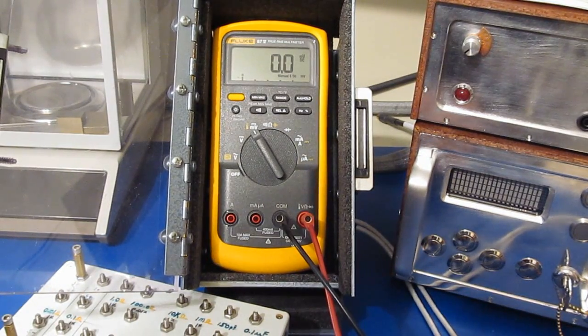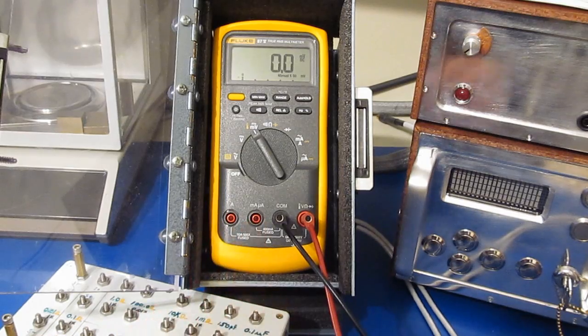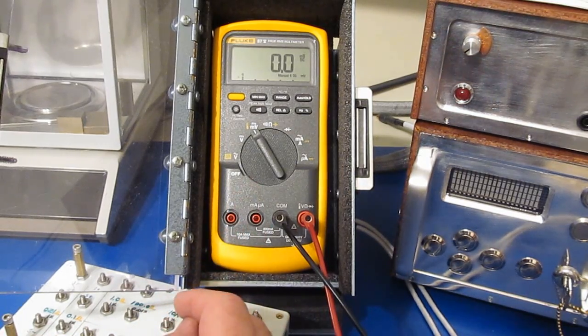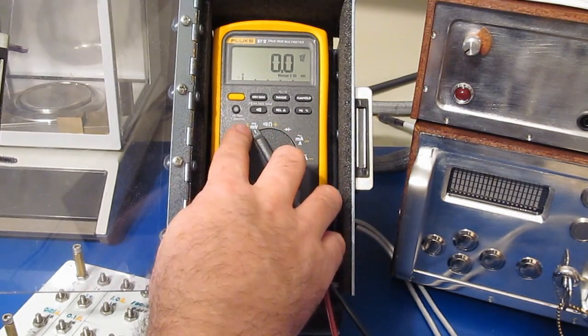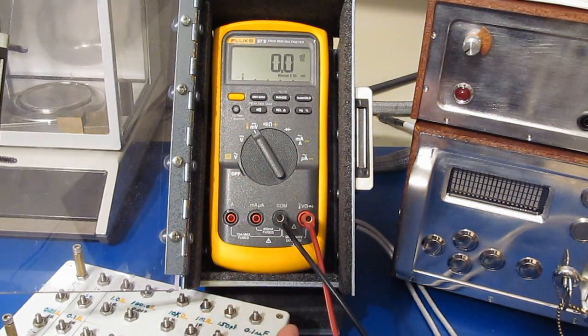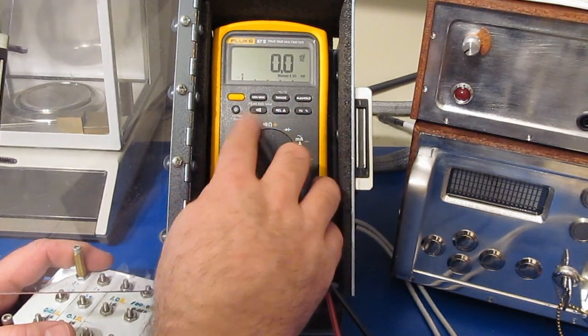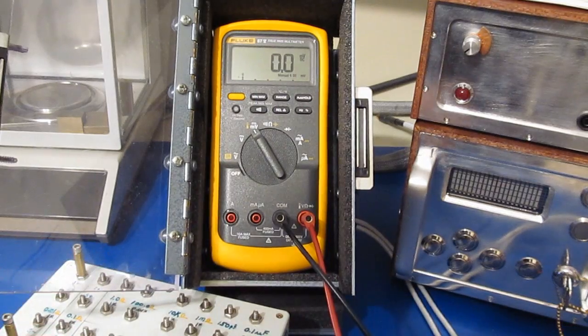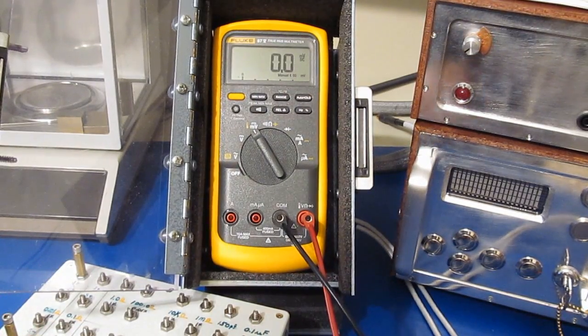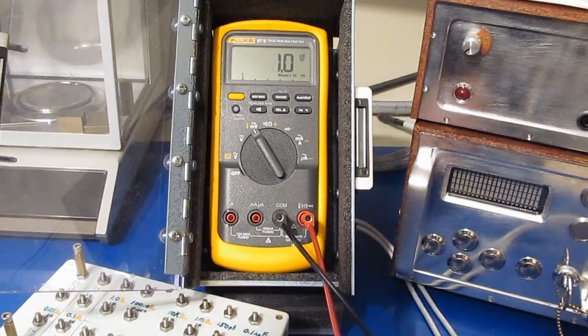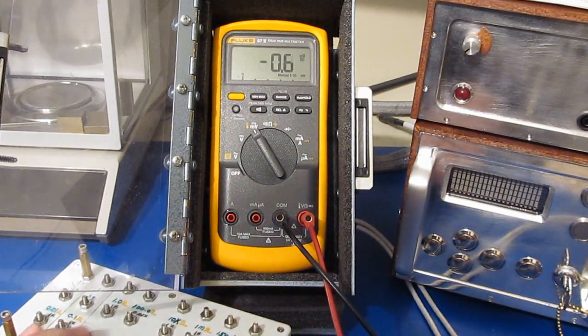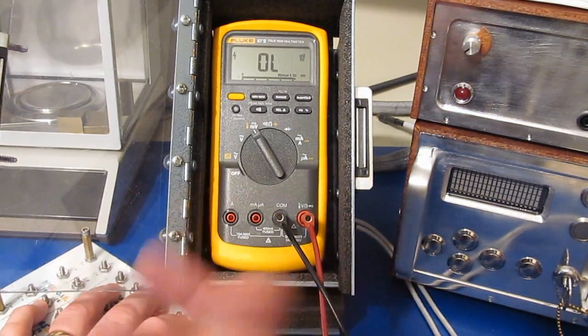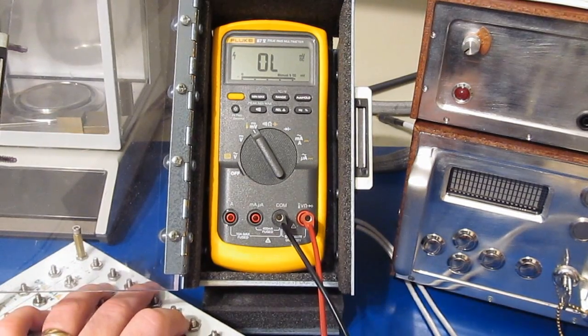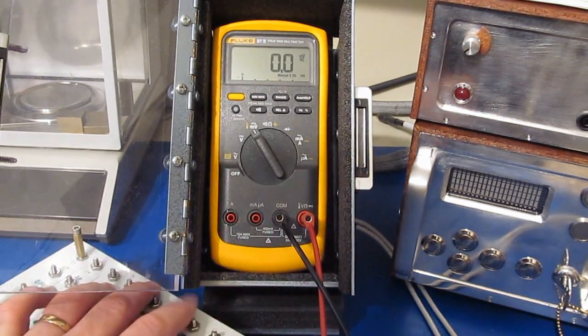So, the person that had sent me the information about the shield had asked another question about this particular meter. They were asking if the meter was in the high Z mode, so it was in the millivolt range, and you overrange the meter, what they say happens with their meter is it'll overrange and then it'll never clear out. So let's just try that in normal mode. What I'm going to do is apply a 5-volt signal to the input of the meter. It should overrange, which it does. I'm going to remove the voltage. It should return to 0.